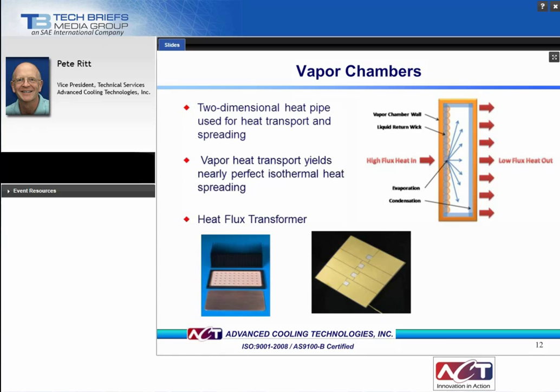Next, we'll talk about vapor chambers. Vapor chambers work similarly to heat pipes but move heat in two directions. As can be seen in the schematic on the right, in vapor chamber operation, high heat flux input causes the working fluid to vaporize. The vapor then spreads in two dimensions. There is wick material all around the inside structure of the chamber.